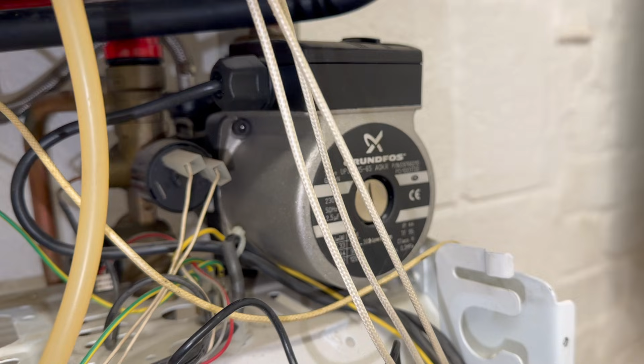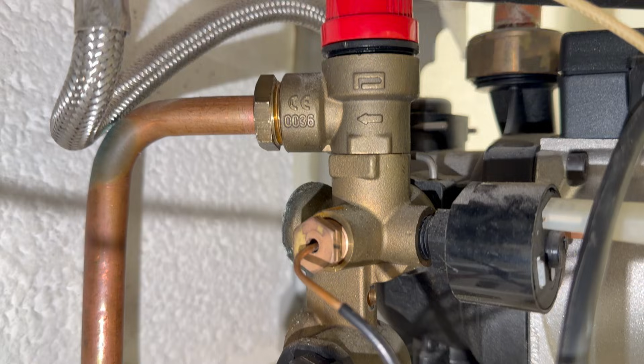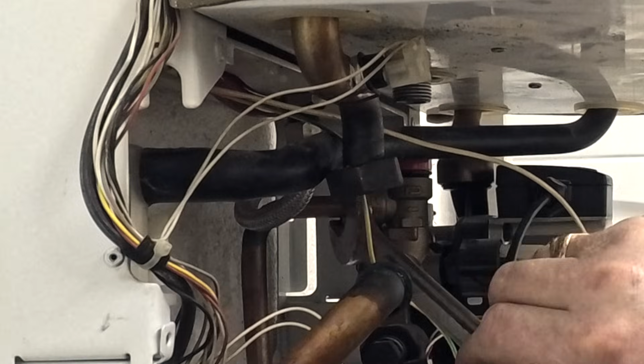Let's get on with that then. I can't find my long reach Allen keys anywhere, so I'm going to take it all out in one unit. First thing I need to do is remove this pipe off the pressure relief valve, then remove this nut here off the pressure gauge. Then I can take the Hall effect sensor off and the wires going to the low water pressure sensor. I'm going to need a 22mm spanner to get onto this nut.